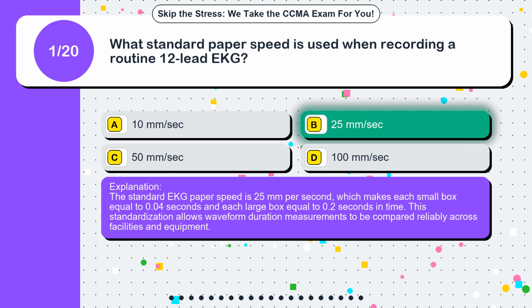The standard EKG paper speed is 25 mm per second, which makes each small box equal to 0.04 seconds and each large box equal to 0.2 seconds in time. This standardization allows waveform duration measurements to be compared reliably across facilities and equipment.